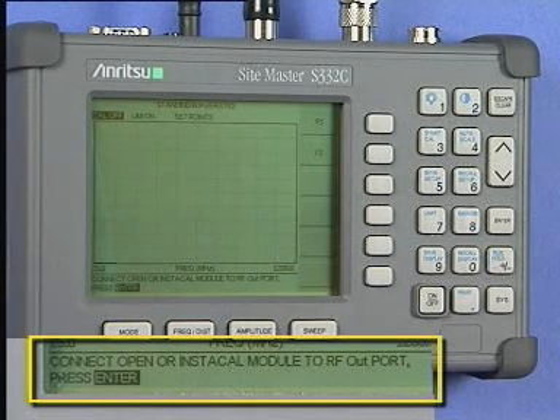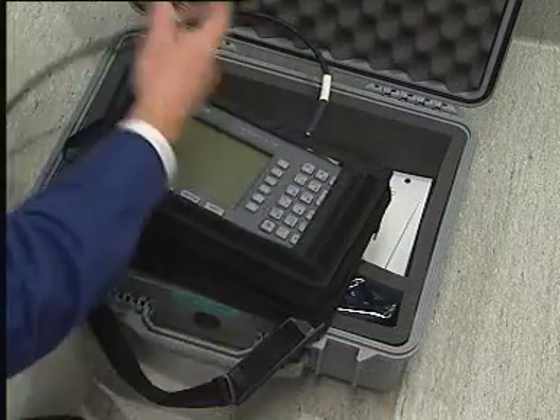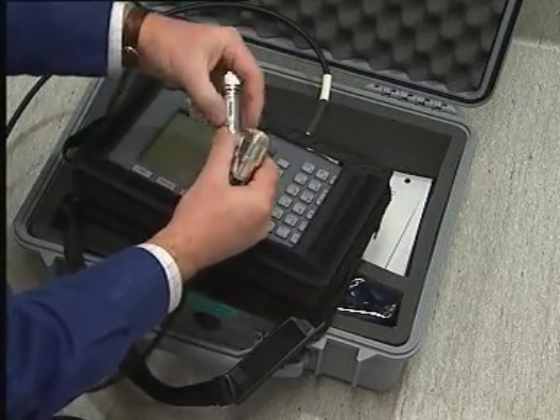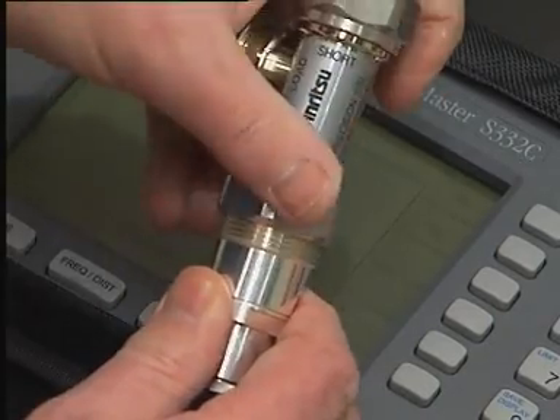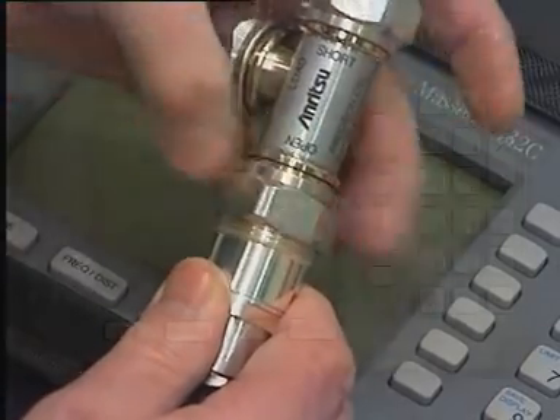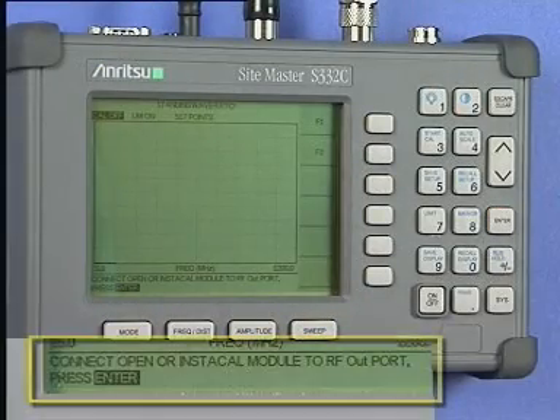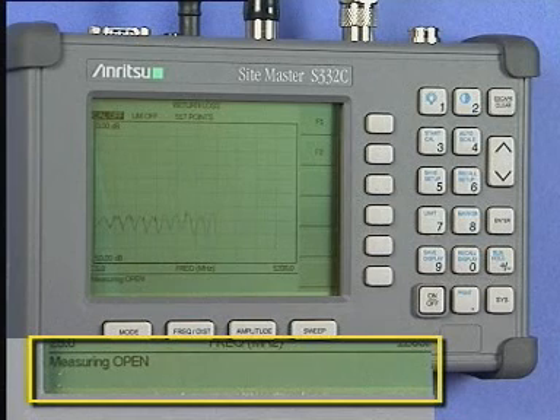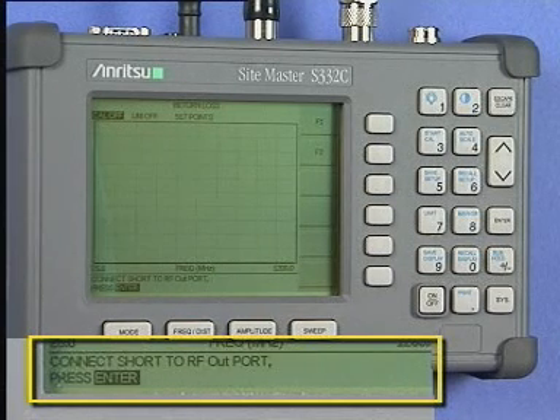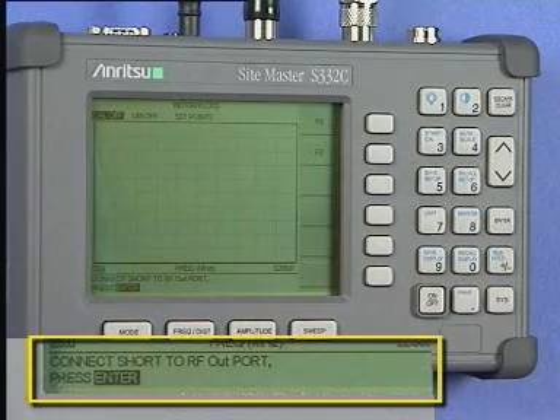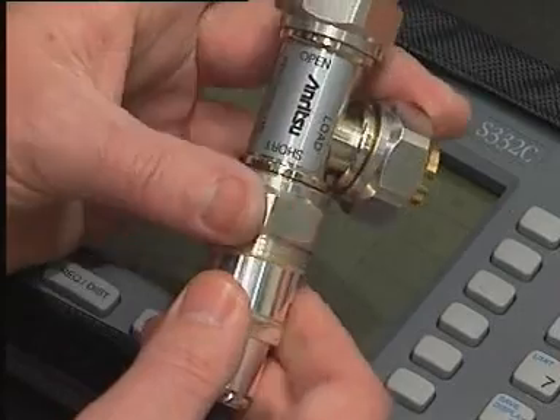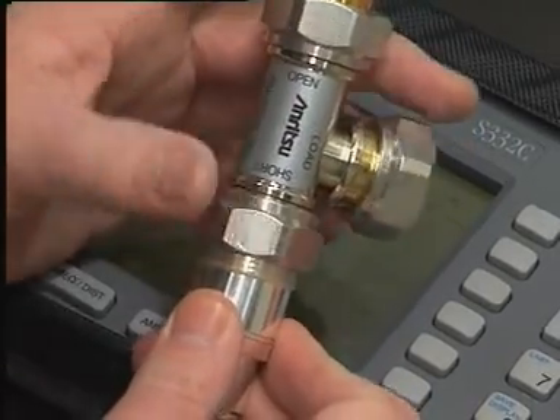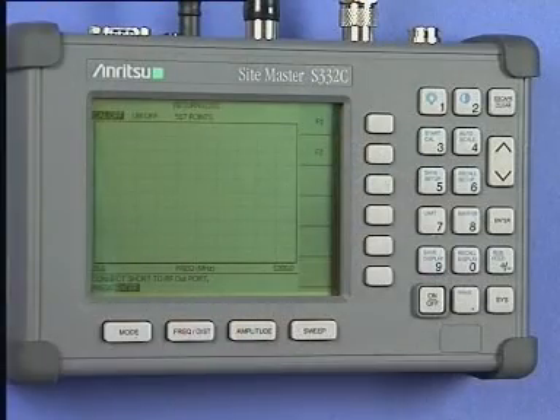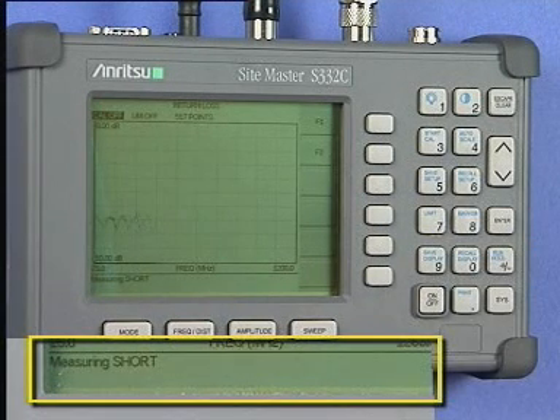At the bottom of the screen you will see the text Connect Open or Insta-Cal RF out port, which is asking you to connect the calibrated open circuit to the extension cable connected to the instrument. When you have done this, press the Enter key and the instrument will sweep and measure your chosen band of frequencies. After a few moments, the Sitemaster will prompt you with the message Connect Short to RF out, which is asking you to connect the calibrated short circuit to the extension cable. When you have done this, press the Enter key and the instrument will again sweep and measure.